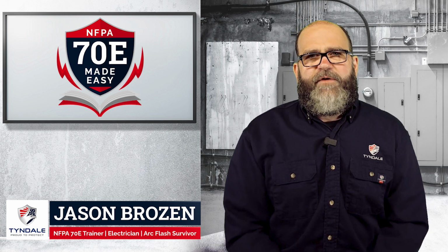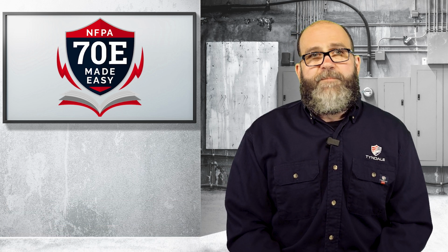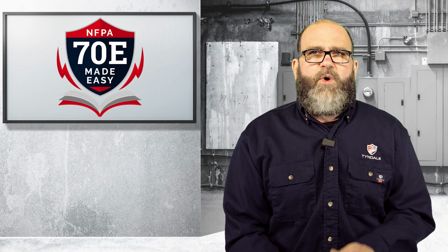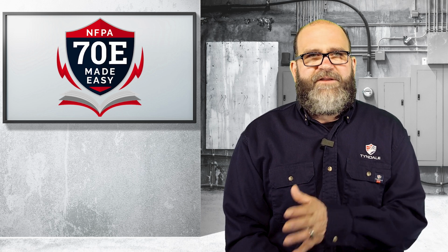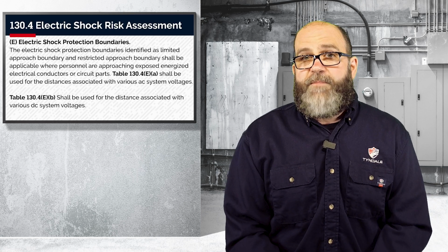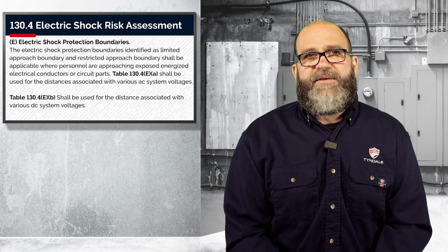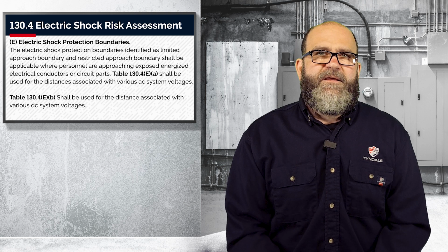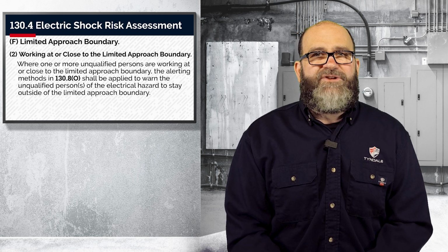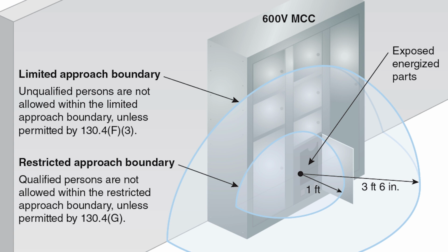A little bit of review up front, but today we're going to talk about one of the most important steps to keep you safe, which is Article 130.4 E, F, and G. This is the electric shock approach boundaries, and it's one of the most misunderstood topics in the 70E. Last time we covered E through F. In this episode, we're going to talk about G, which describes your shock protection boundary known as the restricted approach boundary.